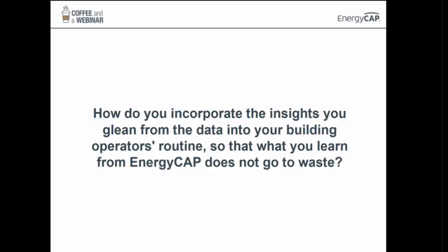And another one was we're working with one of the largest cities in the country and looking at their interval data from their city hall building, a building that most people would recognize on site because it's very iconic. We spotted something that their own operations people hadn't spotted, and that was the same kind of a problem. 5 a.m. was when they were hitting the highest peak of the day consistently because of this morning wake-up period.